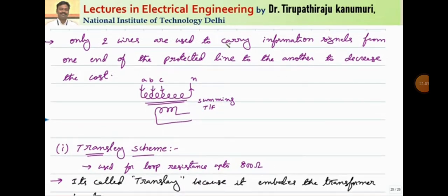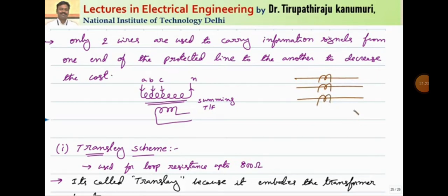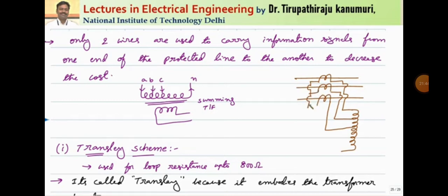Only two wires are used to carry the complete three-phase information. For this, we use a summing transformer. The secondaries of the CTs are connected to the primary of the summing transformer. For a three-phase line with phases A, B, and C, the currents Ia, Ib, and Ic enter the primary. The net sum of these currents introduces the flux, and this flux links with the secondary to induce EMF in the secondary side. The current that passes through the neutral channel is equal to Ia plus Ib plus Ic.